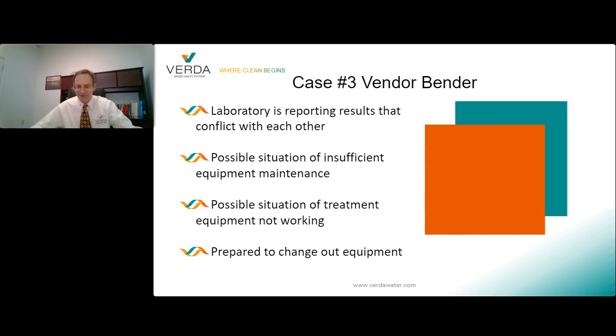microsiemen threshold. Perfect. Hardness, however, was a red flag, right? 30 milligrams per liter? It's supposed to be less than 1. We're way over the maximum hardness for final rinse water. So the protocol was to retest, and this was done. Results came back, again, exceeded the limit.